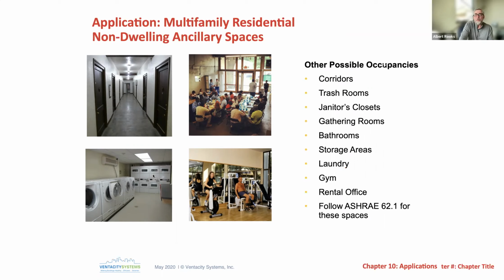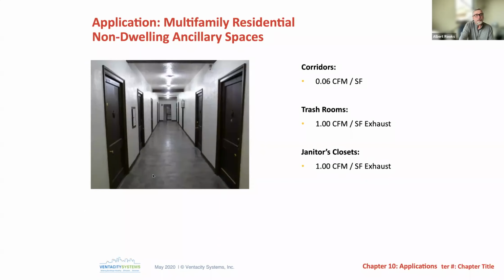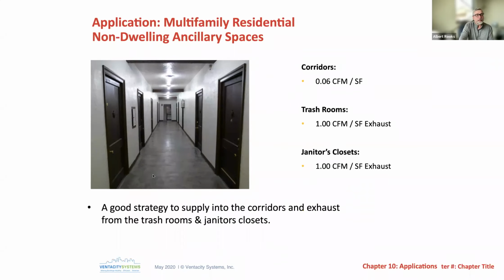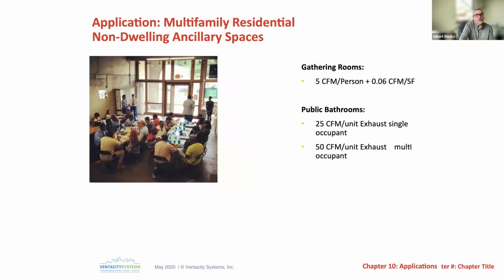We need something with more flow, and especially a room like the upper right-hand corner that could get quite a few people in it, right? At that point, we need a lot of ventilation. And so this is our opportunity to do it. There's ways that these things are designed, you know, corridors 0.06 CFM per square foot and so on. That's all kind of through the design. And so these are all great strategies to kind of go through that.